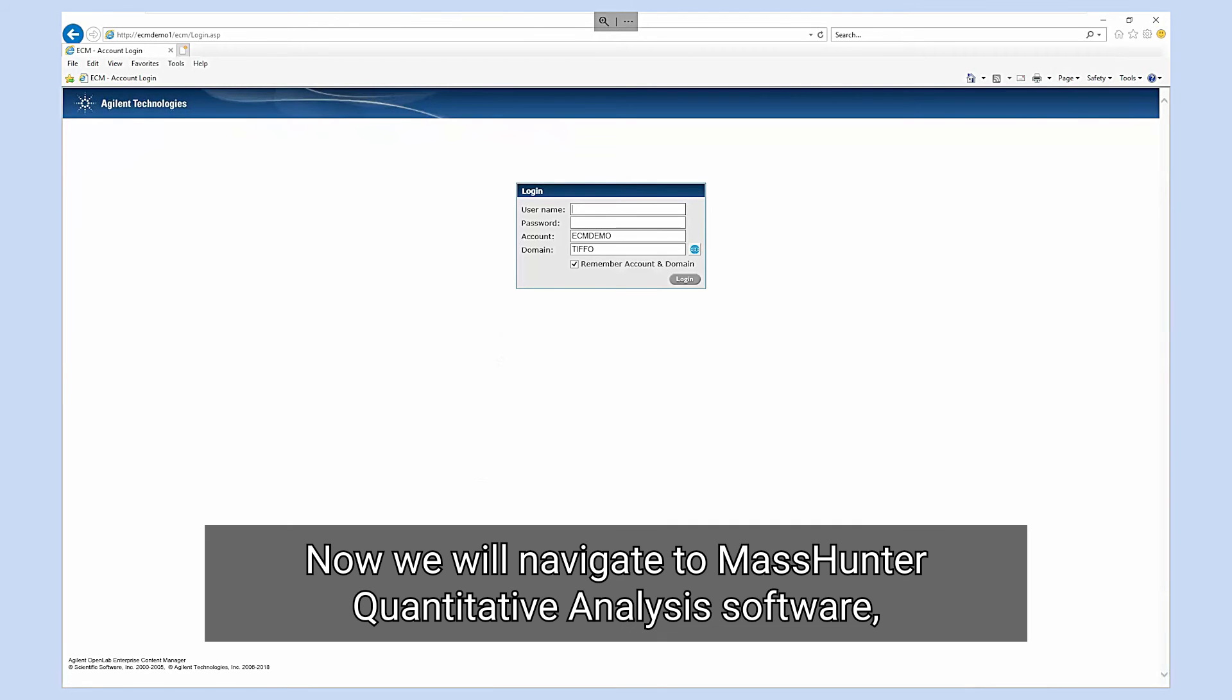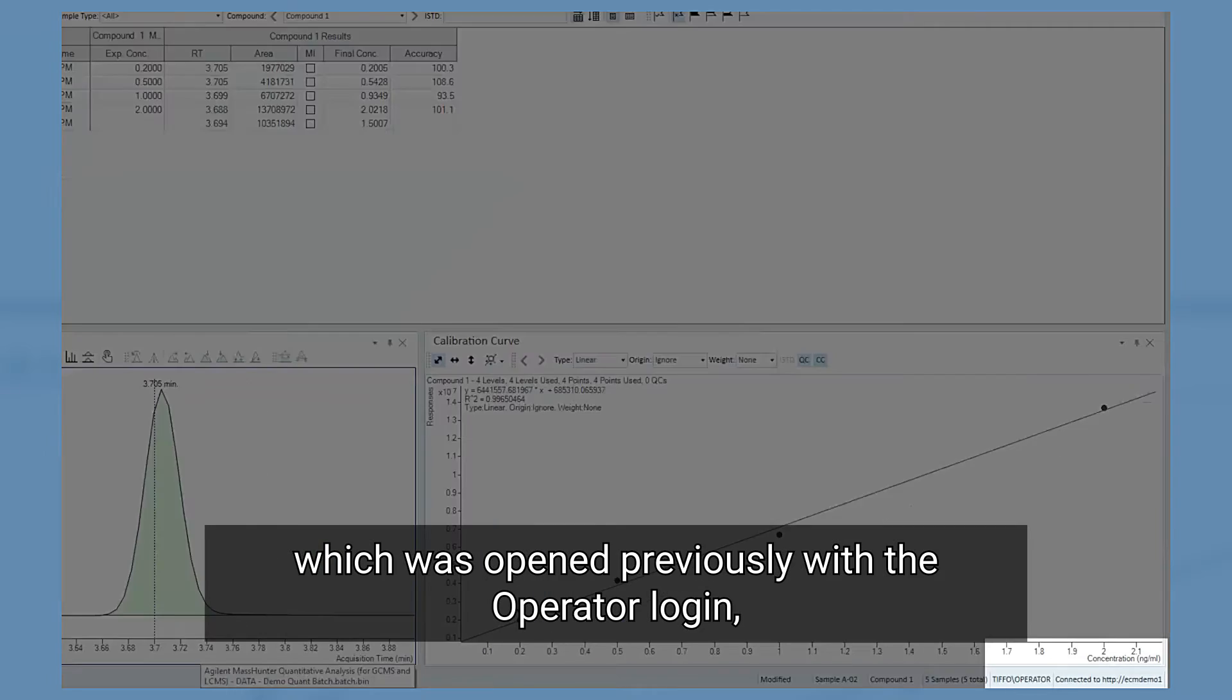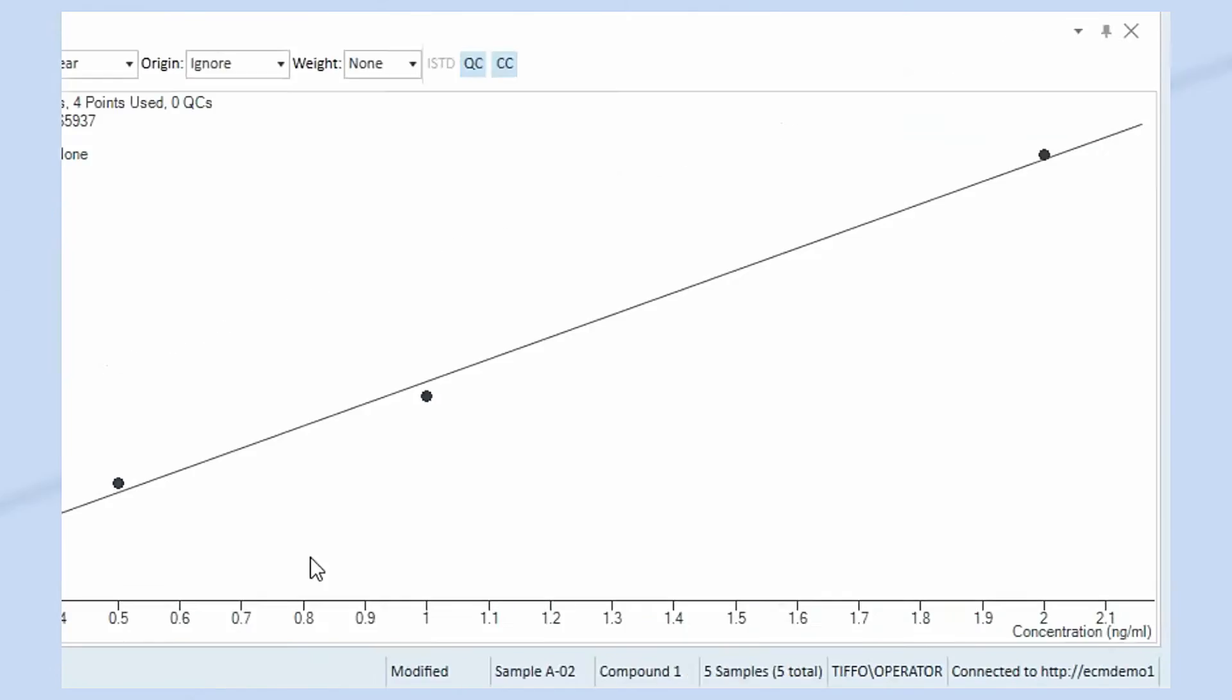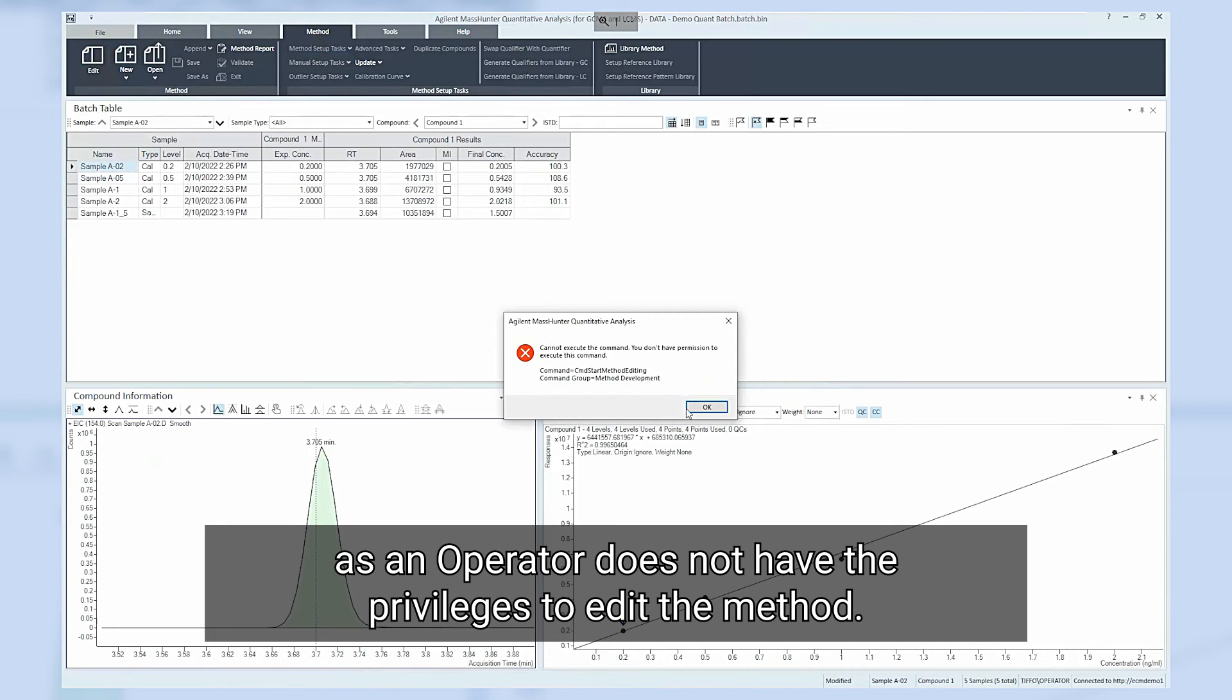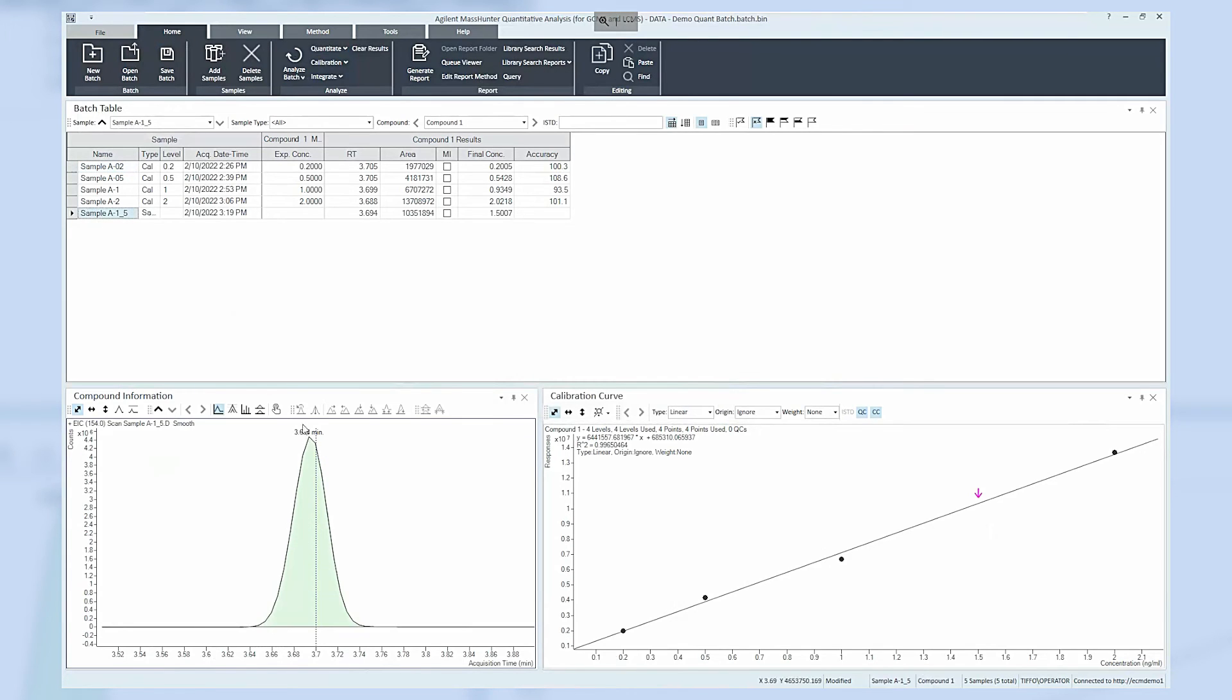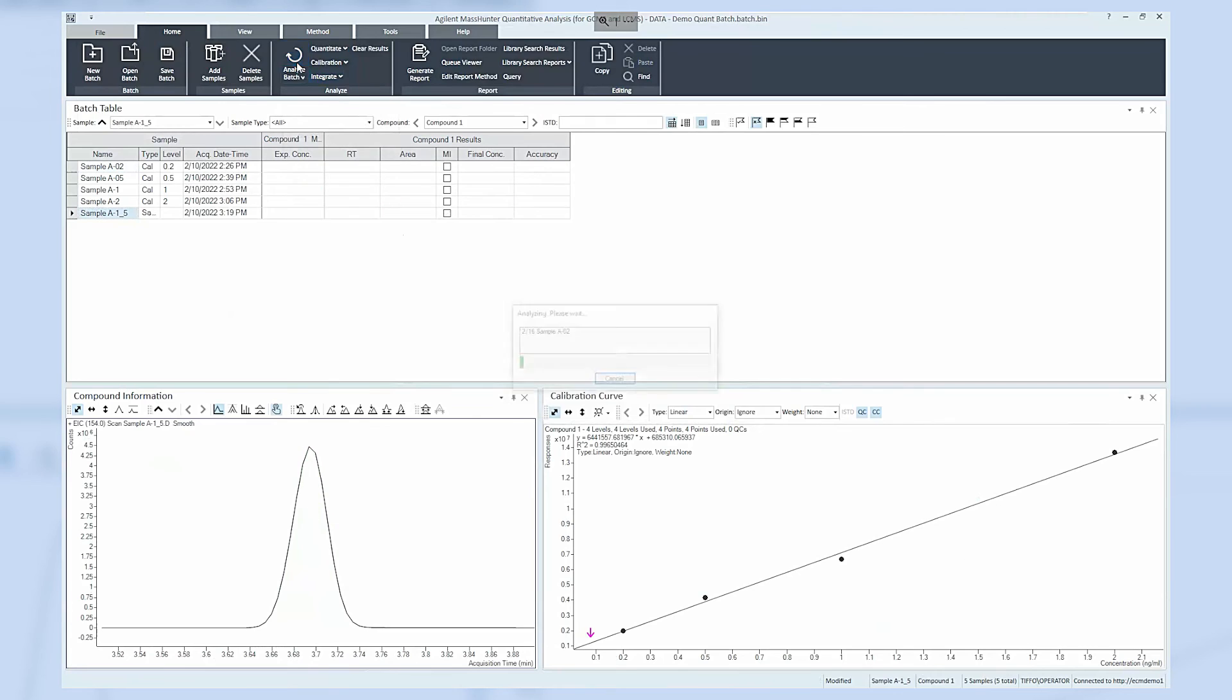Now we will navigate to the MassHunter quantitative analysis software which was opened previously with the operator login shown in the bottom right corner. To edit the method click method then edit. Here an error message pops up as an operator does not have the privileges to edit the method. However operators can still integrate. Here an obvious change to the previous integration result is performed which we will see later in the audit trail report.